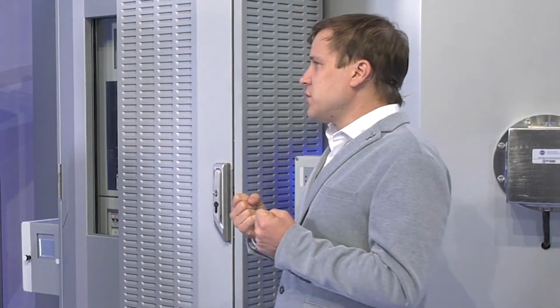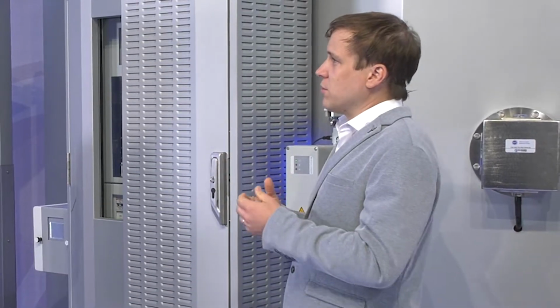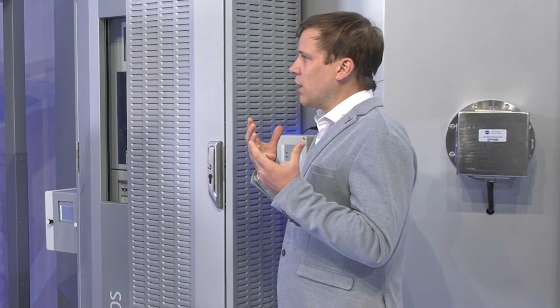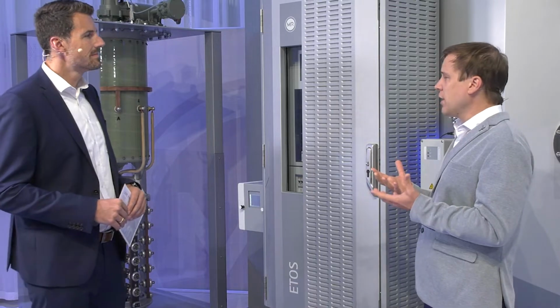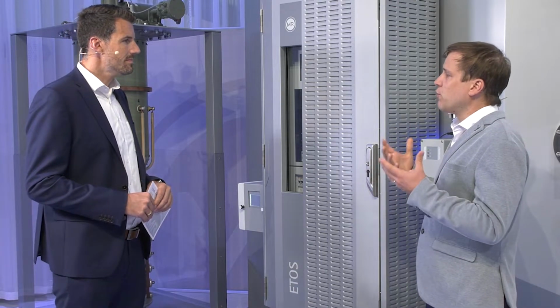For the smart sensors, I want to point out the four main topics. For transformer monitoring, we have the fiber optic temperature measurement, the MSense FO, our brand name. Then for the DGA, we have the different gas sensors to detect the gases inside the power transformer. Then the bushing monitoring, for monitoring the status, the condition of your bushing, and the MSense VAM, for example, for the tap changer monitoring. All of these can be easily integrated, and it doesn't have to be Reinhausen sensors. It's going to be easier if you take it from one hand, because then it's, let's say, like a plug and play solution. But you can also integrate any kind of other sensor.